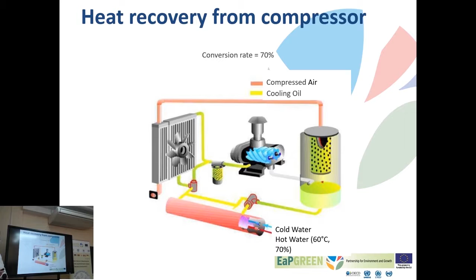The better approach is to use a shell and tube or a plate-type heat exchanger in the oil circuit to heat water at first, to recover heat as hot water between 60 to 70 degrees, which is very nice for cleaning, many purposes, or for sanitary water, and only take the surplus heat, which we cannot recover, to the radiator. So actually to reuse the heat from the compressor for heating. This is really effective, pays back in a maximum of 3 years.